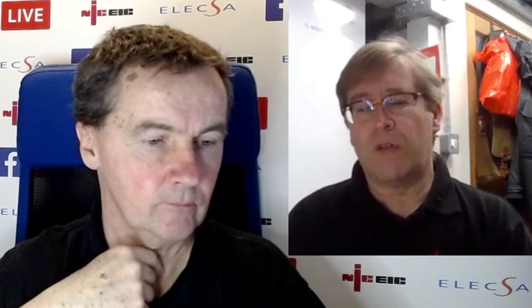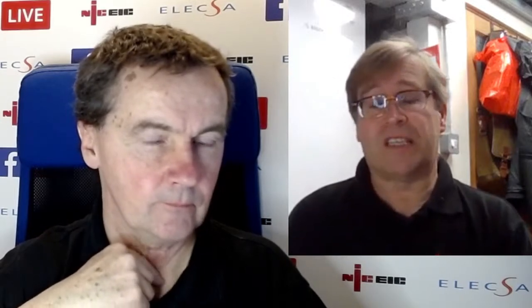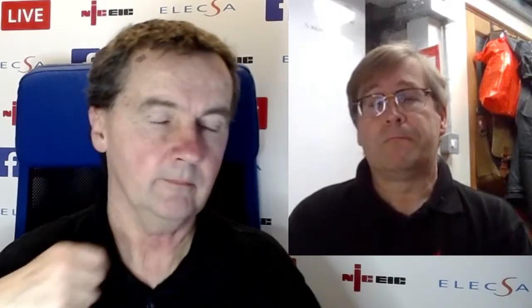There is a reg as well, 415.1.2 I think, that says you shouldn't rely on the sole use of an RCD. Do the sanity checks, because there could be an underlying problem which needs to be investigated and rectified later on. So although we might be curing a symptom, not the problem, if we just put it on there, we've got to make sure there isn't a problem.